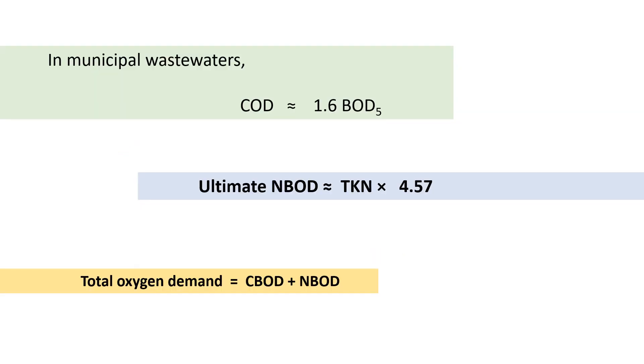In municipal wastewater, the value of COD is almost 1.6 times more than BOD5, so COD ≈ 1.6 × BOD5. The ultimate nitrogenous BOD equals total Kjeldahl nitrogen multiplied by 4.57. This is a very important formula. The total oxygen demand equals C-BOD plus N-BOD, meaning carbonaceous BOD plus nitrogenous BOD.